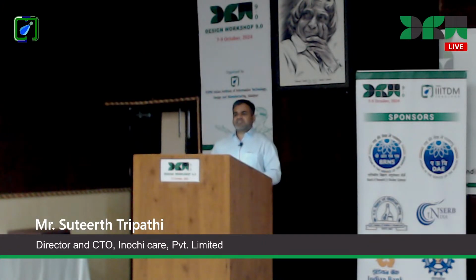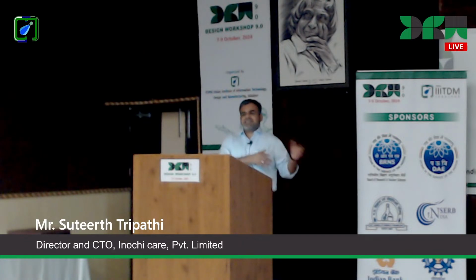You must have set some upper temperature and humidity limits? Yes, ma'am. For that, once we are designing the system architecture, we need to take into account exactly what are the user settings where the product will be used. If it is going to be used outdoors, it might be used in Kashmir, in Tamil Nadu, or in the Sahara Desert. So we need to take into account that those devices have to work all the way from minus 20 degrees centigrade, maybe up to 50 degrees centigrade.